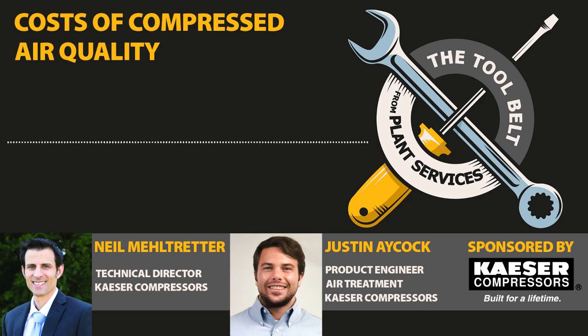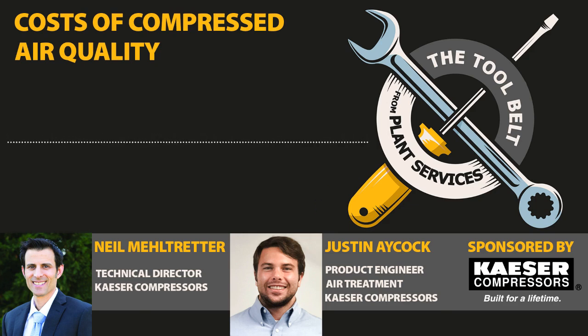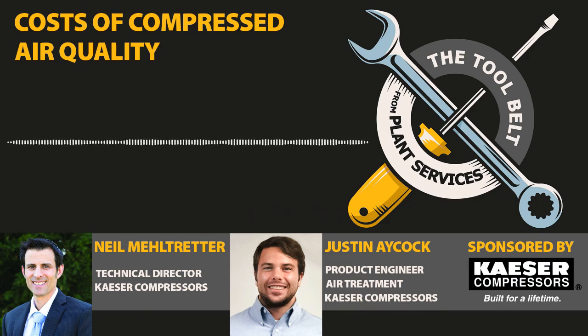And now if you use, let's say, call it inferior materials or materials that are going to rust and scale, now you're going to have the potential at that point of use, and then you're going to have a higher scrap rate or more downtime because now you have production equipment that is affected. So that's really, I think, the biggest thing for me. Copper, stainless steel, aluminum, those are really the best materials to choose for ensuring air quality in your system.